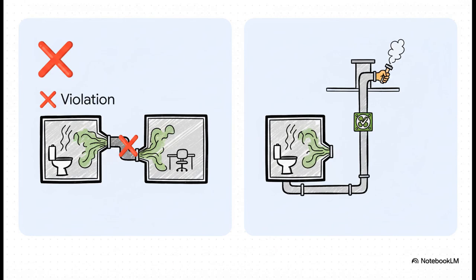Okay, this next one is a huge health violation. If you connect a toilet's exhaust into the main return air duct, you're literally pumping contaminated air all through the building. It is absolutely forbidden. The only way to fix it is with a totally separate exhaust fan, and you better believe they're going to pull out a smoke pencil to make sure it's working.